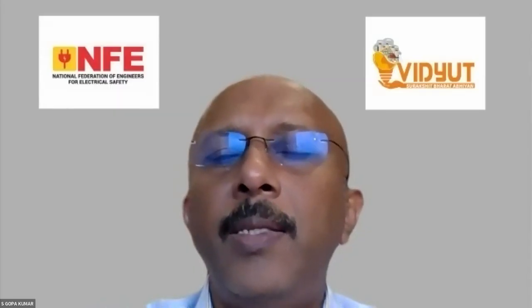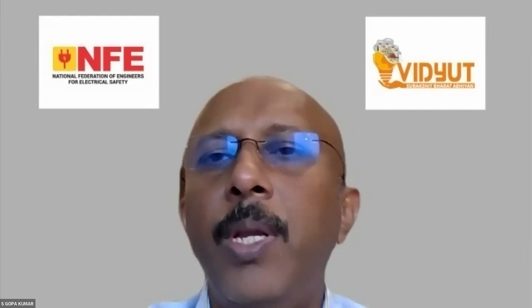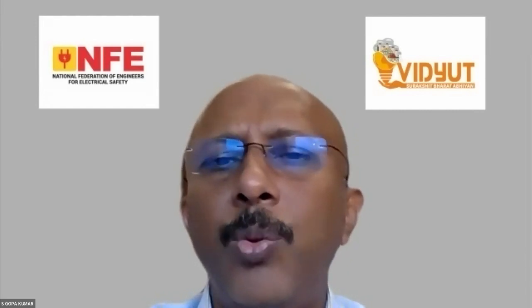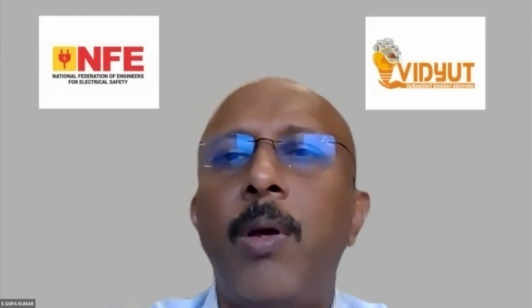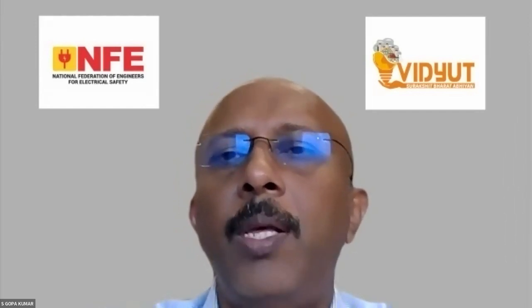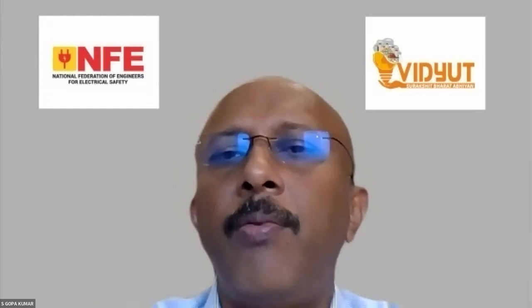Okay. Sir, Krish is saying, following up on your answer on his question, IT earthing, how do we test insulation monitoring devices? Would it be self-test by the device itself, or would it be only through periodic testing and cross-checking the values of insulation monitoring devices and an IR tester? Yeah, Mr. Krish, there is a related standard available, and the respective test is also included in the standard. I think 2-3 types of tests are there. I am not sure of the exact type of test, but these are already documented in the standard, and you should refer to those documents.